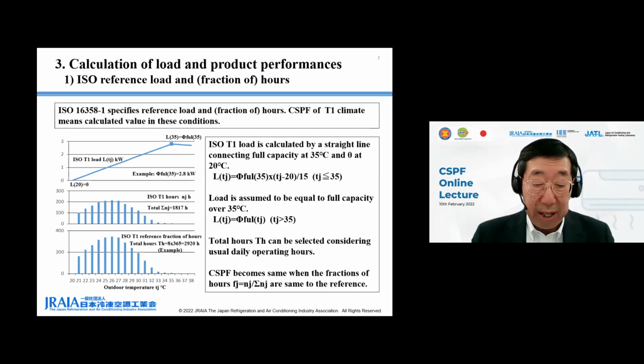ISO 16358-1 specifies reference load and hours. CSPF of T1 climate means calculated value in these conditions. The upper figure shows ISO T1 load at each outdoor temperature Tj. ISO load is calculated by a straight line connecting full capacity of the product at 35 degrees C and 0 at 20 degrees C. ISO load is equal to full capacity over 35 degrees C, based on the assumption that both fixed and variable capacity units cannot increase capacity more than full capacity.